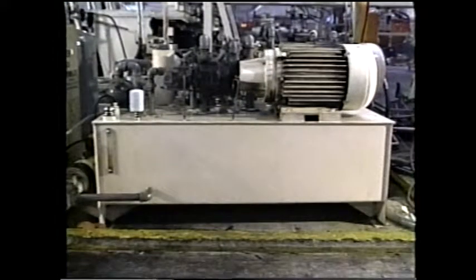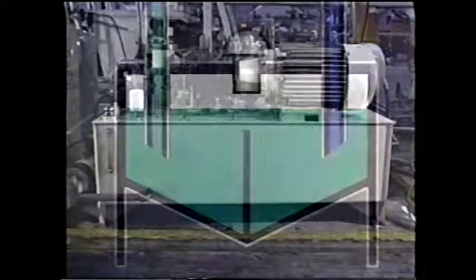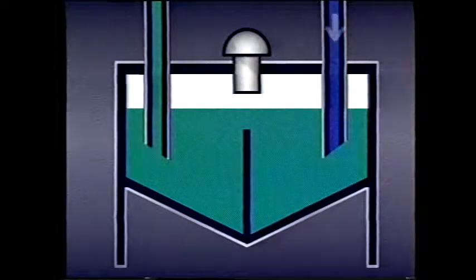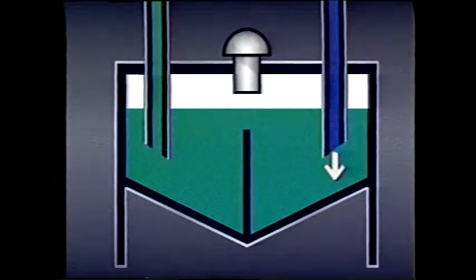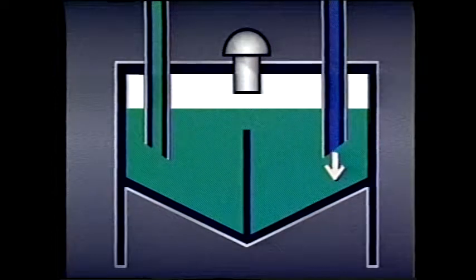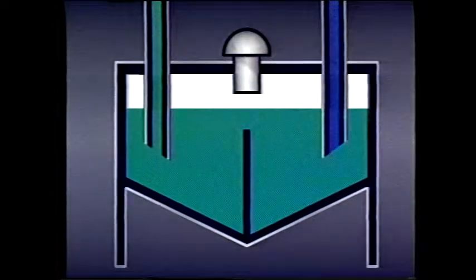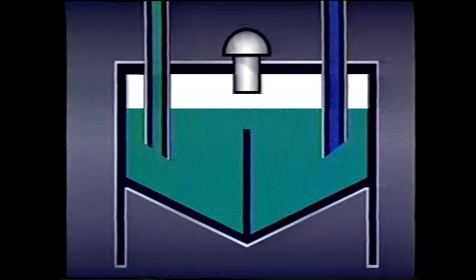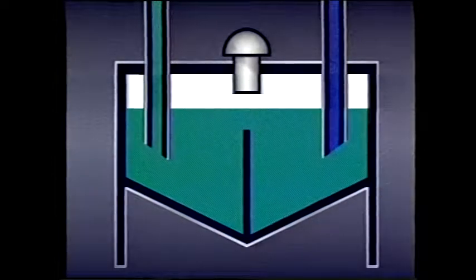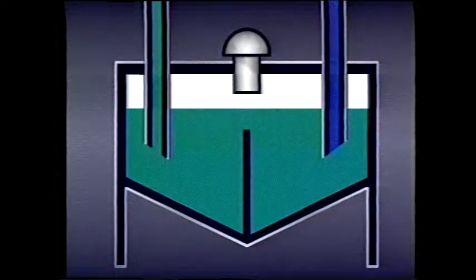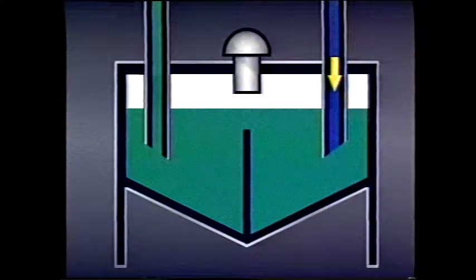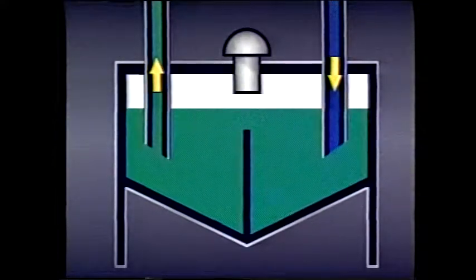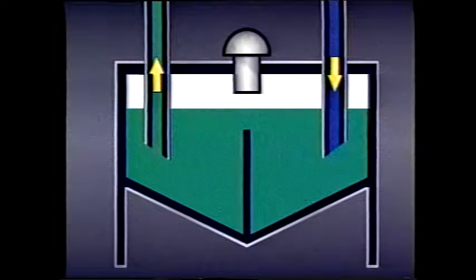Let's begin with the reservoir, often called the sump or tank. Basically, all reservoirs work the same way. Fluid enters the reservoir through return lines that extend below the surface of the fluid. This prevents splashing, which would add air bubbles to the system and could cause pseudo-cavitation. All return lines come in on one side of a reservoir baffle plate that prevents the fluid from being immediately drawn back into the pump.